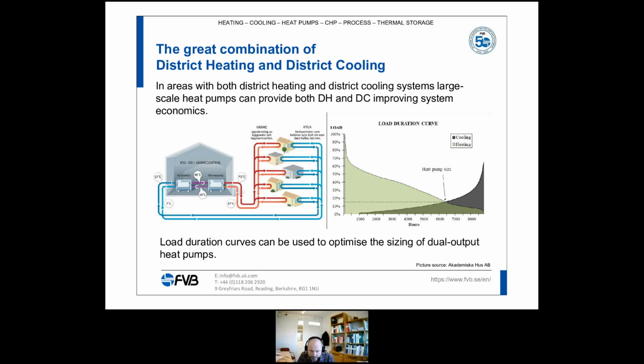Naturally, if you then also have another heat source, it could be sewage water or something else, you could run the heat pump all year long, and that would be the dotted line there. So you're not dependent on the district cooling. And if you do that, this heat pump in this example would then provide you 40% of the energy of the district heating system.